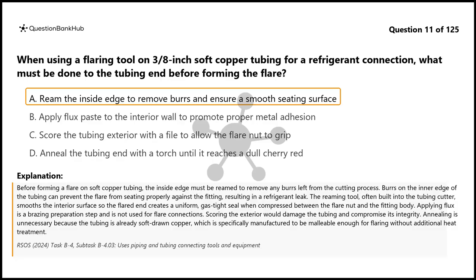Applying flux is a brazing preparation step and is not used for flare connections. Scoring the exterior would damage the tubing and compromise its integrity. Annealing is unnecessary because the tubing is already soft-drawn copper, which is specifically manufactured to be malleable enough for flaring without additional heat treatment.